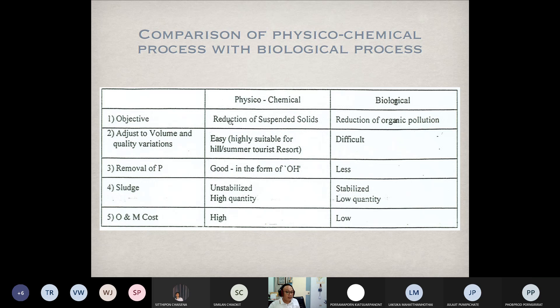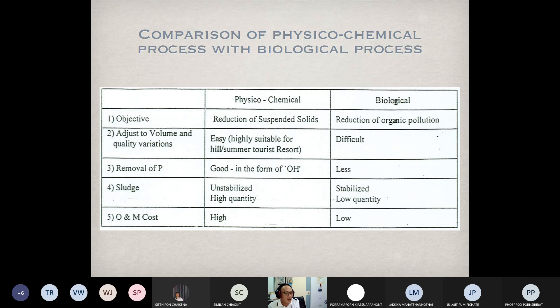So we can flocculate and coagulate those particles and let them settle in the sedimentation tank. This is a combination of chemicals and physical processes — that is why we call it the physical-chemical process. The objective is mainly to remove suspended solids. As we apply chemicals, we can adjust for variations in flow volume and water quality.